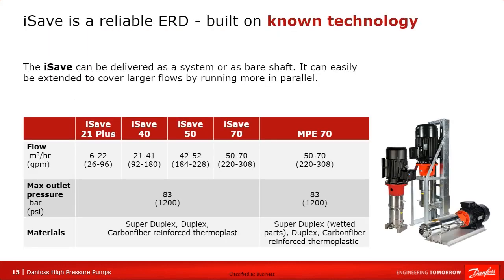Besides the pumps, we also have the iSave ERDs — energy recovery devices. They are built on the isobaric pressure exchanger concept. The iSaves come in different sizes, just like the pumps: the iSave 21 is the smallest, covering 6 to 22 cubic meters, all the way up to the iSave 70. We also have the MPE 70, which is a pressure exchanger concept used more in bigger RO systems.